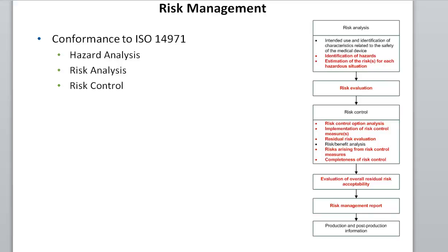Inherent by design would be finding the source of that shock and fixing it, so it's a little bit different than a protective measure. And then information for safety. That's where you get into labeling, packaging, and warnings for the user. It doesn't really prevent the risk from occurring. It's simply education. So the idea is you're supposed to evaluate the risk and choose your option in that priority. You should first identify if it is possible to resolve that risk through safety by design. If not, it's not cost effective or appropriate, then you should consider protective measure.